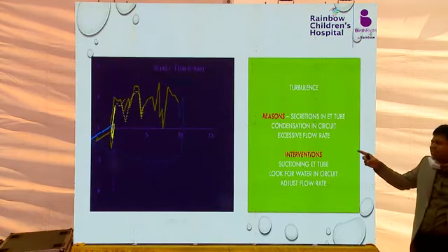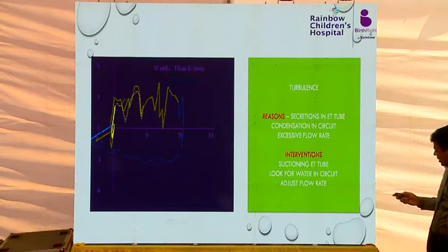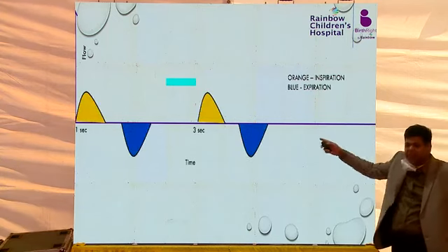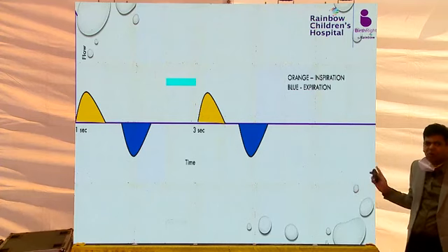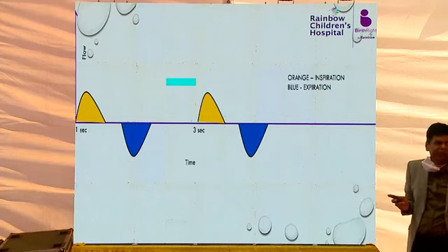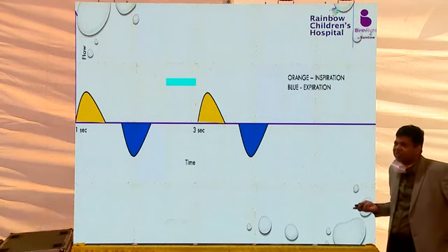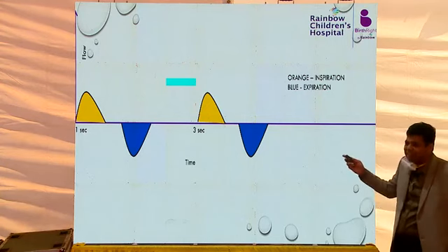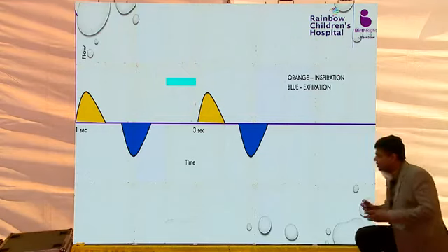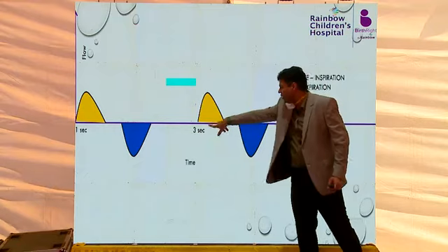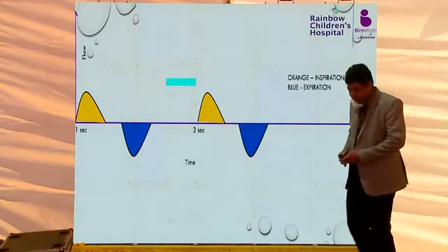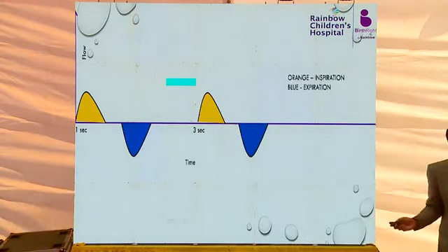This I think we have discussed, the tracheomalacia, water, everything. Okay, this is just for revision. The problem here, this is a flow scalar waveform. It's a long TI. See, the flow has stopped here, but the expiration is happening from here. So the TI is too long. So you will decrease the TI so that there will be no gap.